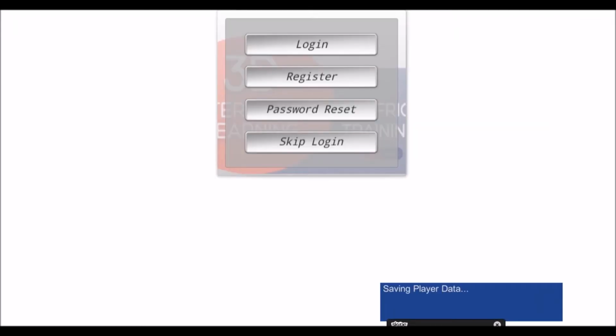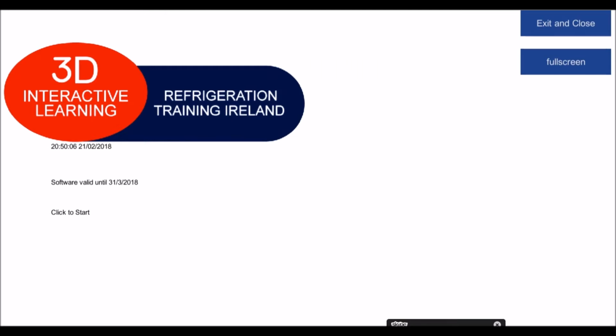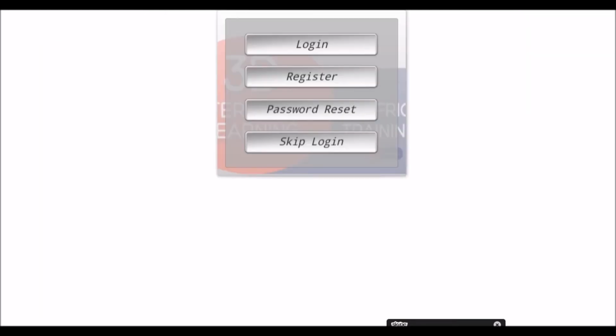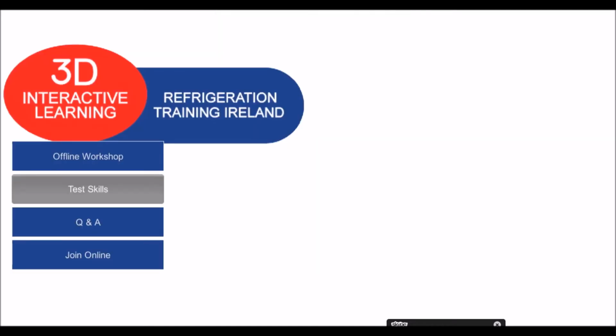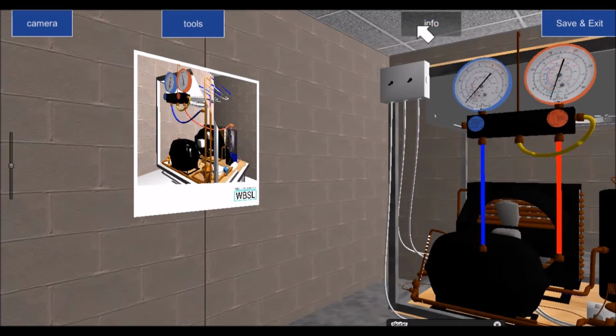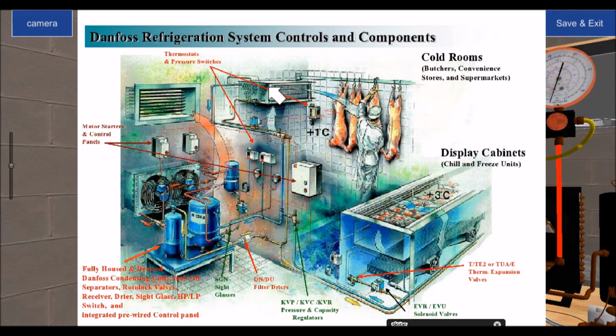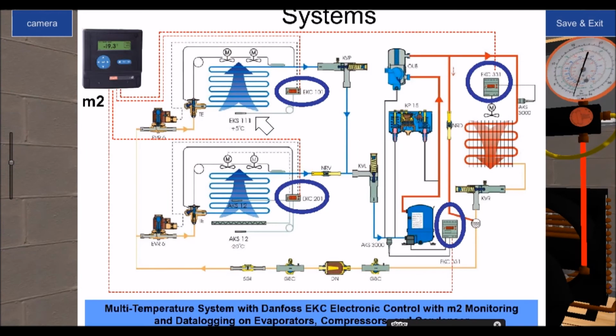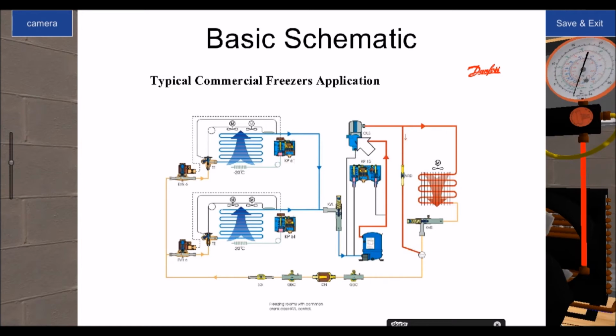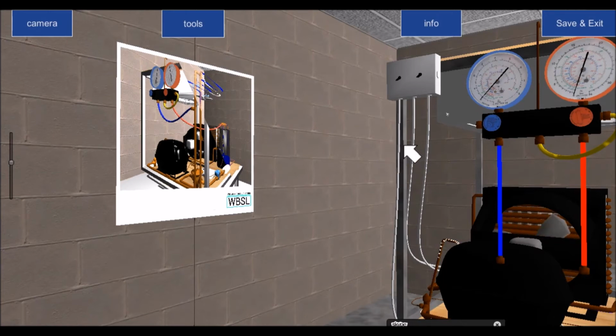Now, don't worry if you get frustrated and can't answer those, or you do really badly, because what I'm going to do at one stage with you is go through each one of these components. So for example, this is representing an oil separator, and I'm going to explain that to you. This represents a pressure switch, a dual pressure switch, high and low pressure switch.